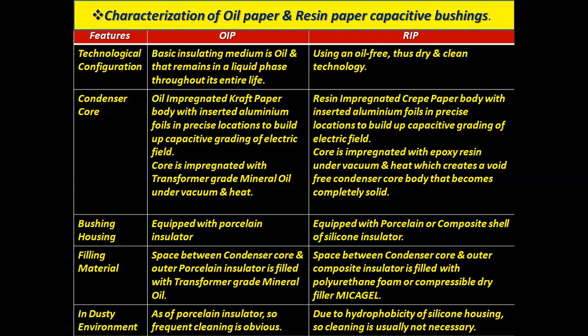In a dusty environment, a porcelain insulator requires frequent cleaning. Due to the hydrophobicity of silicone housing, cleaning is usually not necessary. But if you use a porcelain insulator, then you have to clean frequently, in the case of OIP bushing.